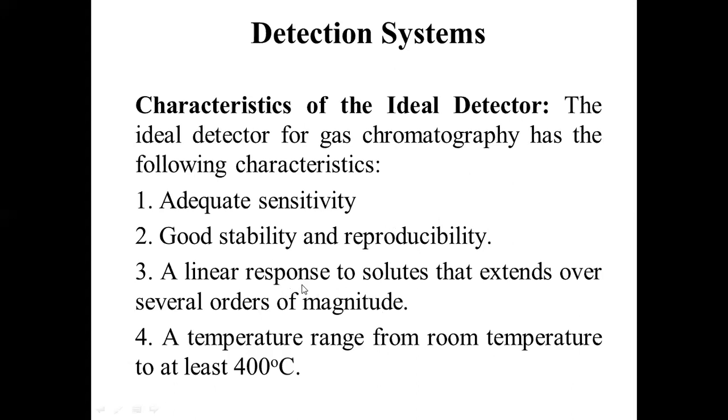And if you introduce a 10 ppm sample or a 100 ppm sample, the signal given by the detector must relate to the order of magnitude of the solute. The quantity of the solute must be directly proportional to the order of magnitude of the signal given by the detector. So, linear response. And it must have the capability to withstand temperatures at least up to 400 degrees Celsius.